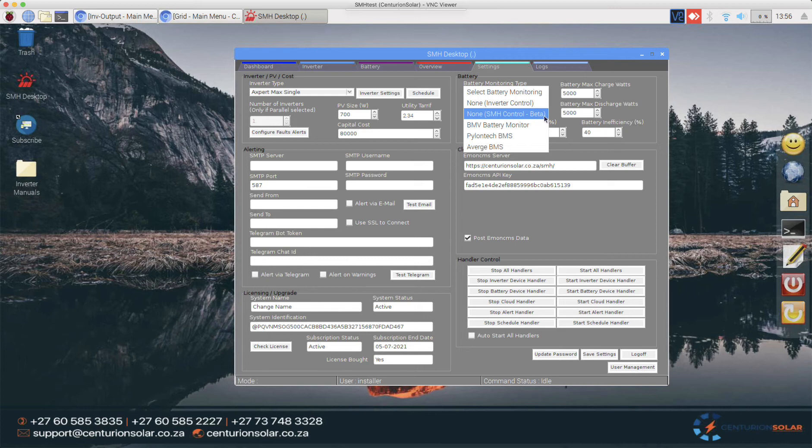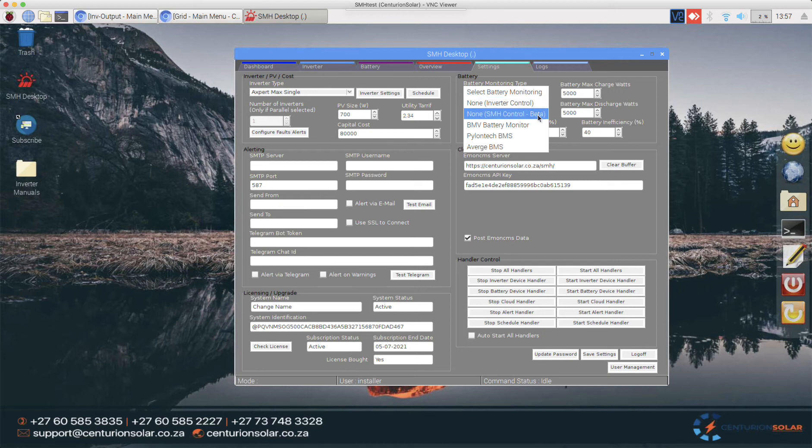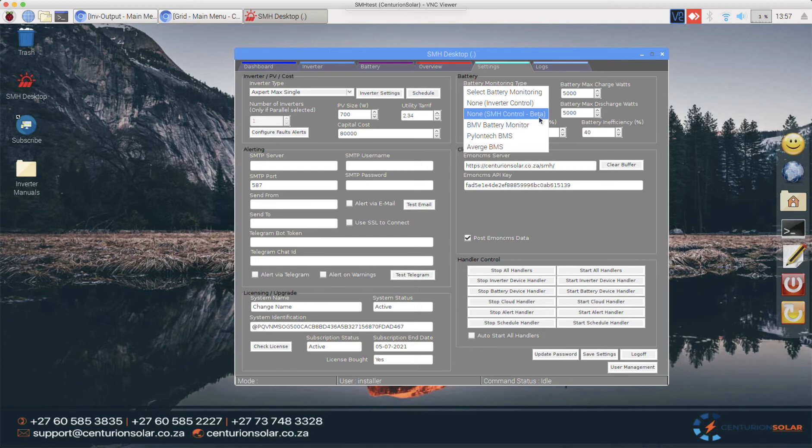Know that this is a beta version at the moment so what this does is it basically checks when the battery is full or a hundred percent it gets a set point and then it starts doing coulomb counting to work out mathematically what the state of charge is. Way more advanced and way more accurate than the inverter control but this does rely on the fact that the battery needs to reach a hundred percent state of charge every day. In a scenario where the battery does not reach a hundred percent the system will not get a set point to start counting from and then obviously the SoC starts drifting from there so hence this is still in beta.